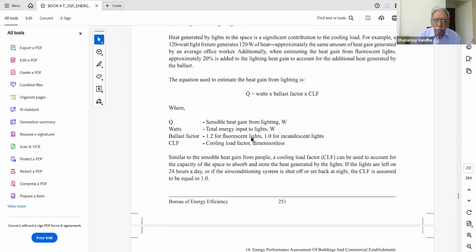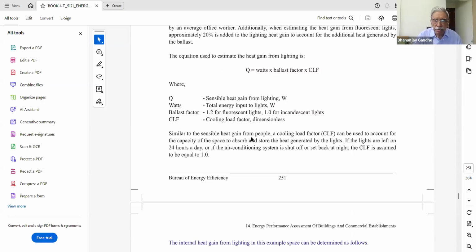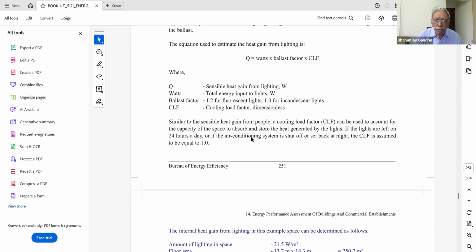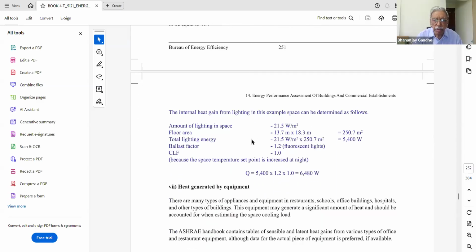So these values are also given over here. How much heat is radiated by a lamp, and also along with the lamp, because this book is old, so it is considering only the tube lights or CFL. So there is a ballast factor for these, which would not be there for LED. And there is the CLF, cooling load factor, which is also specified for this type of construction.